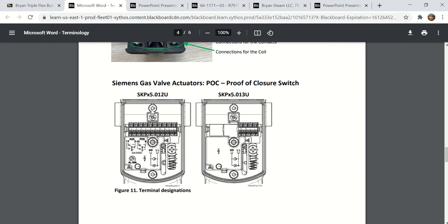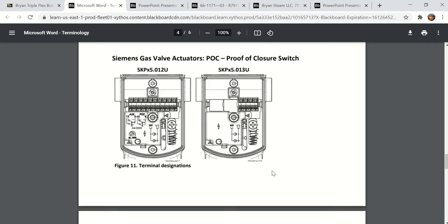Here are the gas valves. This gas valve here is the secondary gas valve. When you see the actuators stacked on the gas valve body, there's actually two actuators. This is an on-off actuator without proof of closure. You don't see the terminals there, but this is an on-off actuator. Here's the power H and L, but you also have terminals 5 and 6, and that is your proof of closure. That's the switch inside there. So on the first gas valve, there is a proof of closure switch to make sure that the valve didn't get stuck. Typically on the secondary gas valve, you don't have to have the proof of closure switch.